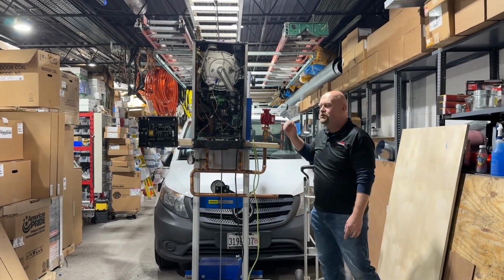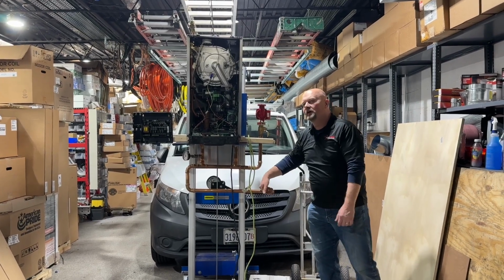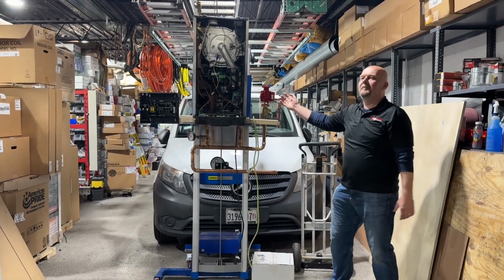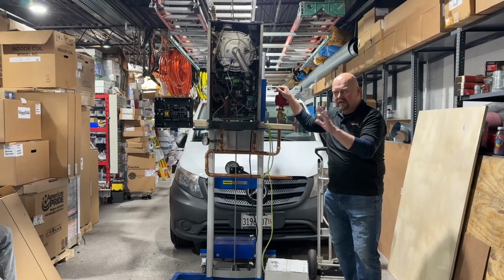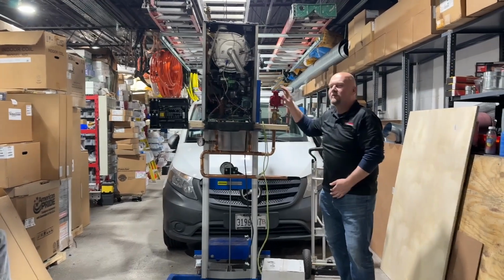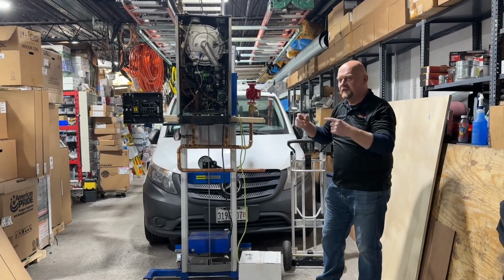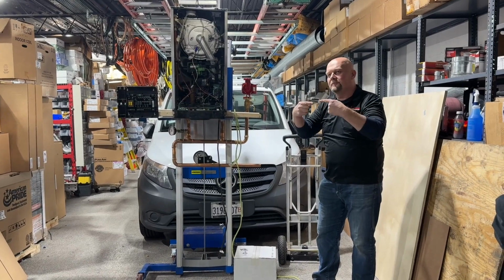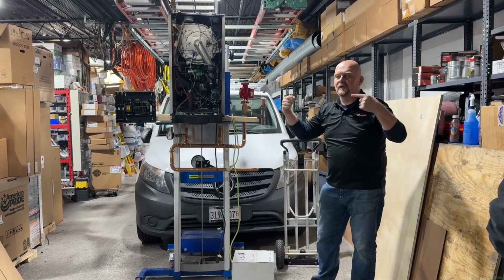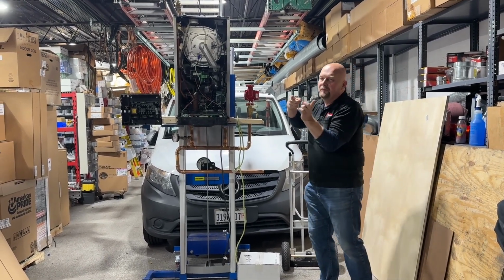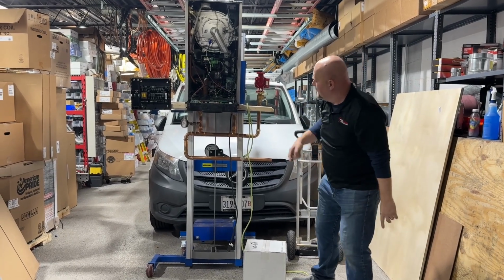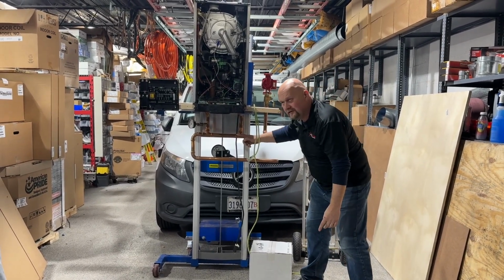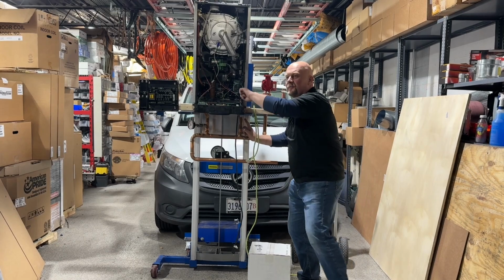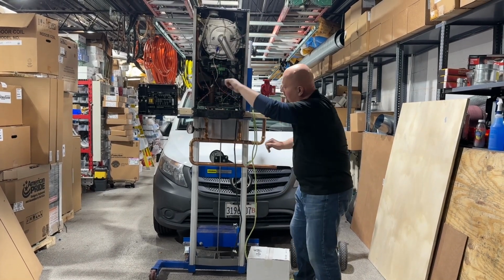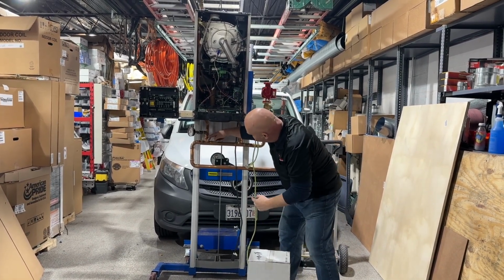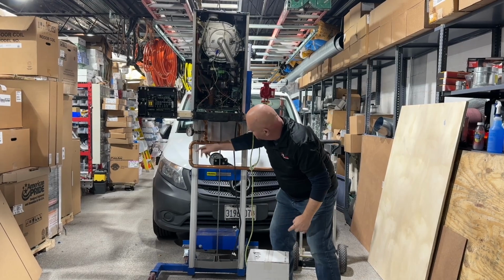Because you can pump away or feed to the supply, or you can pump back into the boiler on the return. Either one is okay. Either one will function. It's just important not to buck the two pumps, meaning you don't want the pumps pumping at each other, you want them pumping along. Because as this pump pushes through here, it'll assist this pump, and when this pump pushes the hot water back through the heat exchanger, it'll also assist this pump.